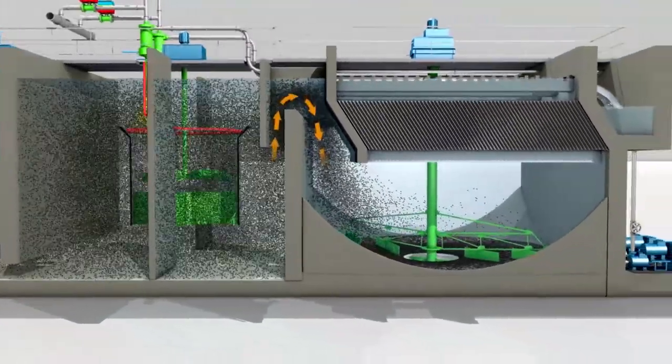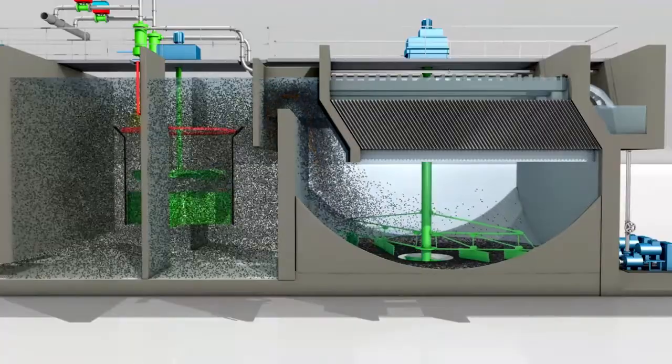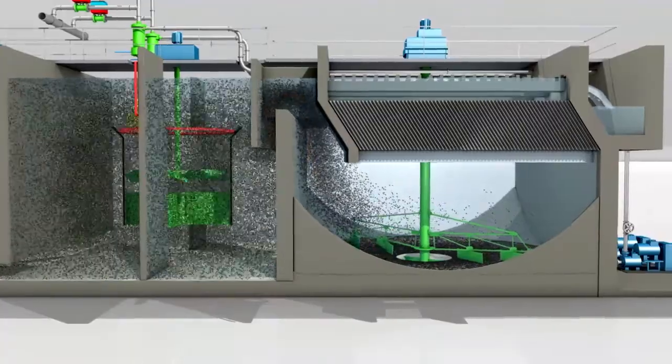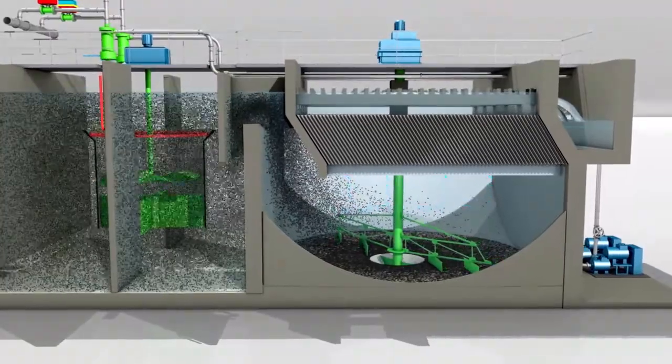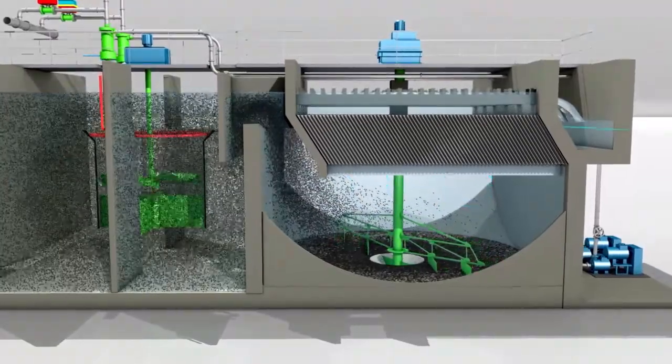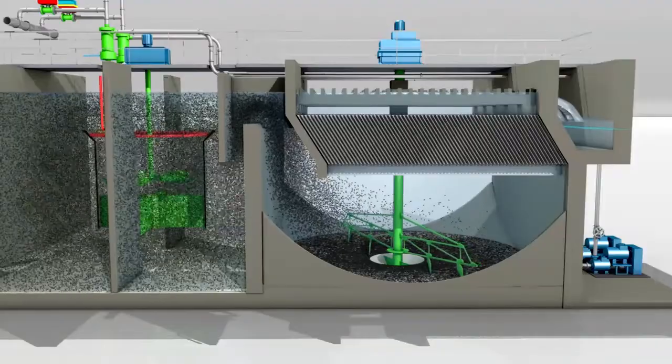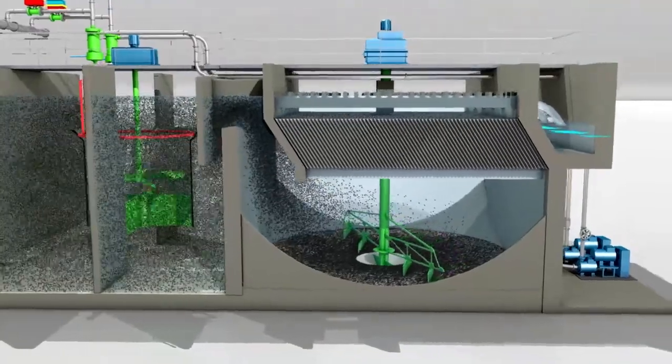The flocculated water then enters the settling tank. The micro sand ballasted flocks settle quickly, while clarified water rises through the lamella and exits the tank via the effluent collection launder. Typical rise rate is 30 to 40 meters per hour, or 12 to 16 GPM per square foot.